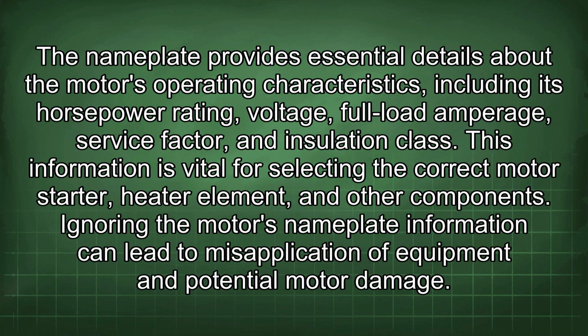The nameplate provides essential details about the motor's operating characteristics, including its horsepower rating, voltage, full load amperage, service factor, and insulation class. This information is vital for selecting the correct motor starter, heater element, and other components. Ignoring the motor's nameplate information can lead to misapplication of equipment and potential motor damage.